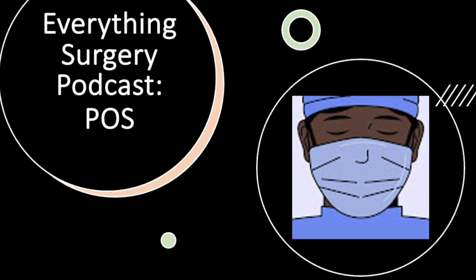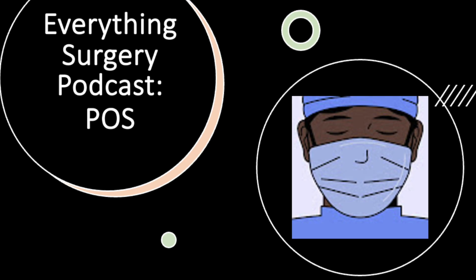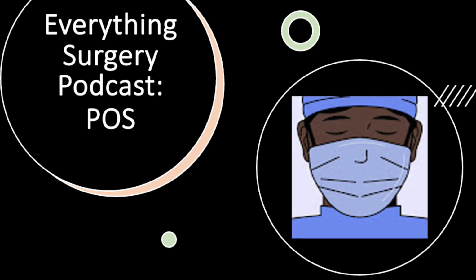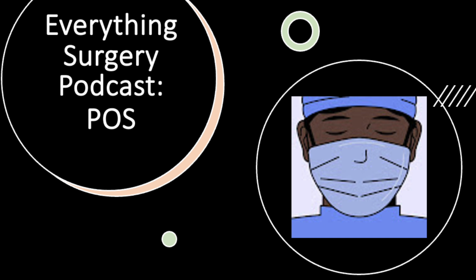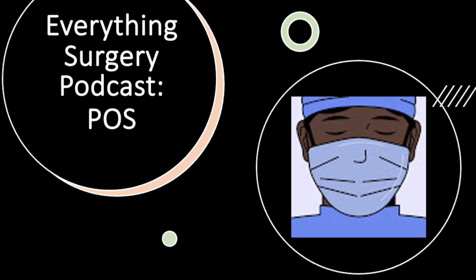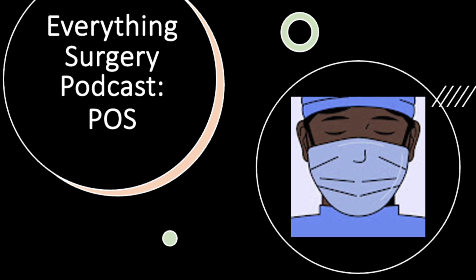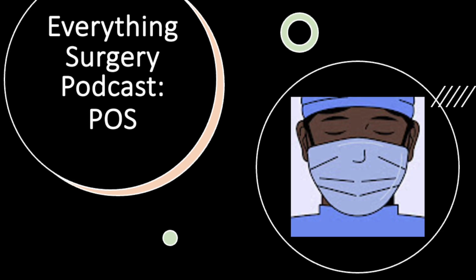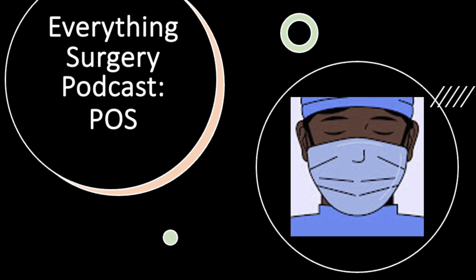In the OR, electromagnetic interference, EMI, and how to handle it. So, what's the big danger in the operating room? It's electromagnetic interference, or EMI for short. Things like electrocautery tools, MRIs, nerve stimulators, even radiofrequency ablations, they all can mess with pacemakers. What kind of problems can EMI cause? Well, it could make the pacemaker stop pacing, which is bad news for someone who relies on it, trigger inappropriate pacing, or even reset the device to a backup mode. Yikes.